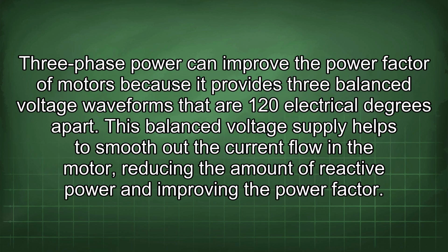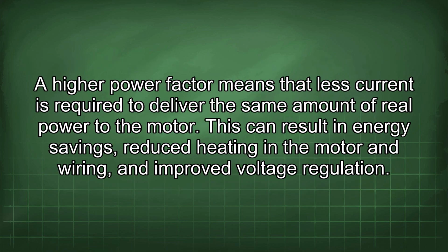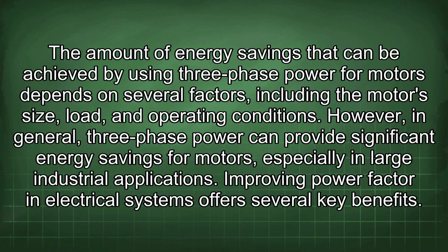Three-phase power can improve the power factor of motors because it provides three balanced voltage waveforms that are 120 electrical degrees apart. This balanced voltage supply helps to smooth out the current flow in the motor, reducing the amount of reactive power and improving the power factor. A high power factor means that less current is required to deliver the same amount of real power to the motor. This can result in energy savings, reduced heating in the motor and wiring, and improved voltage regulation. The amount of energy savings that can be achieved by using three-phase power for motors depends on several factors, including the motor's size, load, and operating conditions. However, in general, three-phase power can provide significant energy savings for motors, especially in large industrial applications.